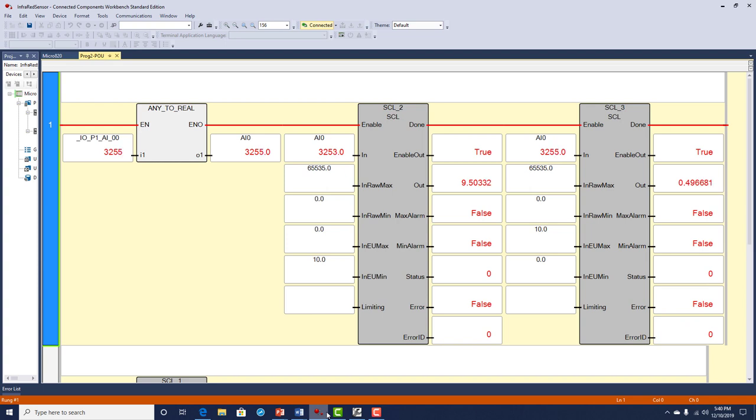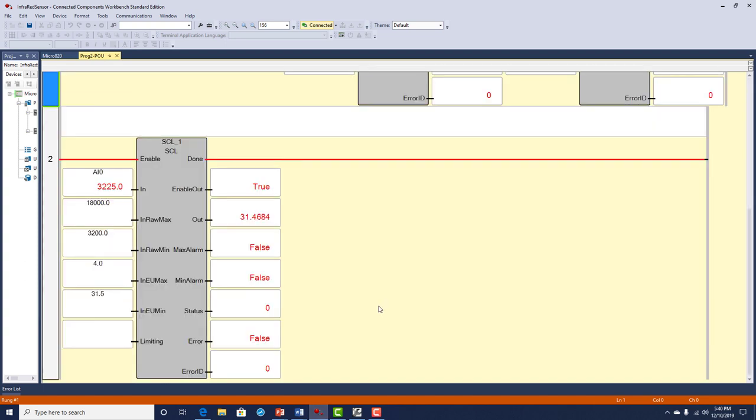Now if I go out to about, I'm just going to have to guess here on 12 inches. Not very linear. You see I'm getting a value higher than 12 inches. And if you look at the curve on this sensor, it's not linear. You would have to do some linearization. You could do that in software. Truth is you're not going to use a sensor like this anytime out on the shop floor in the factory. You're going to be using a sensor that has built-in linearization and adjustments for span range and the whole 10 yards. I will include this lab project in that fourth volume, which is part three of the set for CCW.